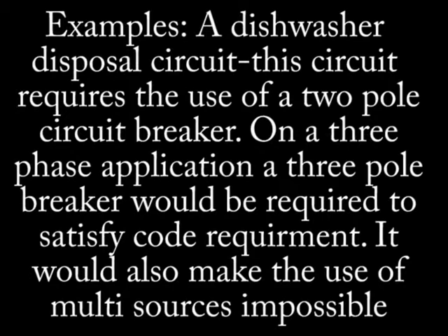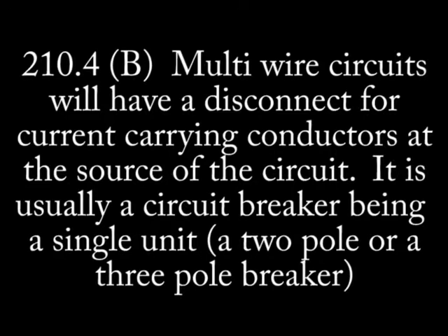The same applies to a multi-wire circuit originating from a three-phase panel. A three-phase air conditioner requires the use of a three-pole breaker. Article 210.4 paragraph B: multi-wire circuits will have a disconnect means for ungrounded conductors at the source of the circuit. This subsection points out that on multi-wire circuits a single unit breaker must be used.